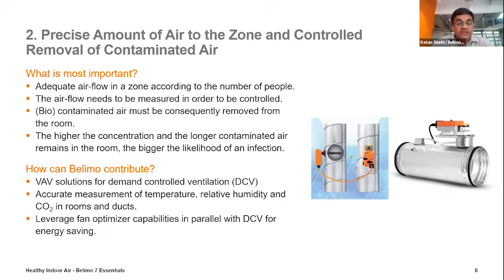So the measures or the solutions that Belimo can contribute is the VAV solution. Mr. Mittal talked about the DCV, demand control ventilation. We have got the VAV offer for that, VAV control mechanism, and again the accurate measurement of temperature, relative humidity and CO2.